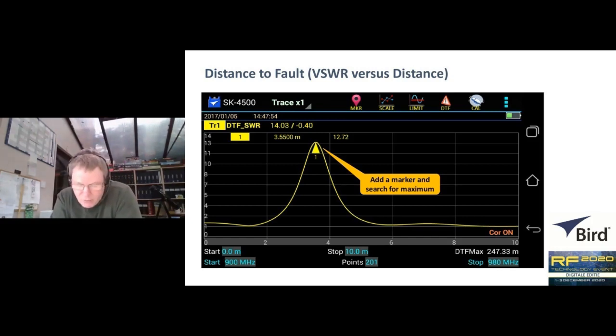It therefore follows that if we know the phase angles of the reflections for a number of different frequencies, and if we know the velocity ratio of the cable, we can calculate the distance at which the reflection, or reflections, are taking place. In our example here, we can see a reflection representing a high voltage standing wave ratio, and you can see the numbers there in the top left-hand corner of the screen, 12.72 to 1. So we have a reflection representing 12.72 to 1 at a distance of 3.55 meters along the cable.